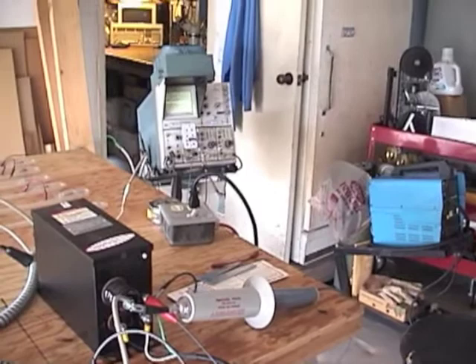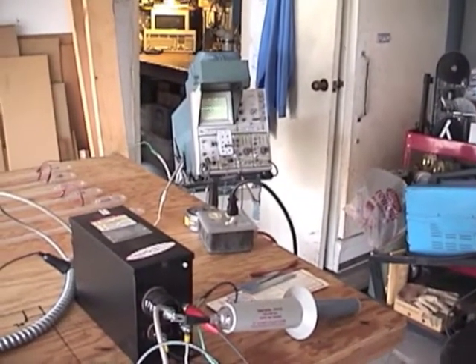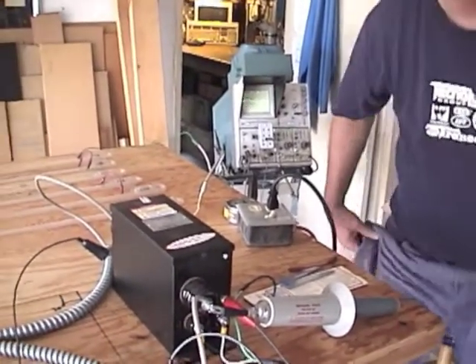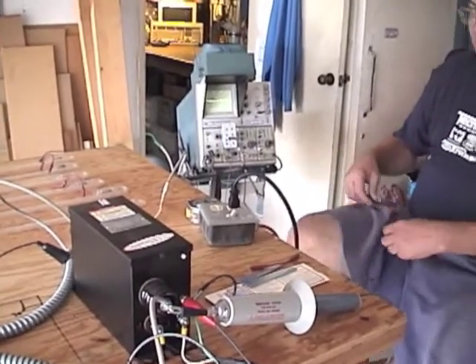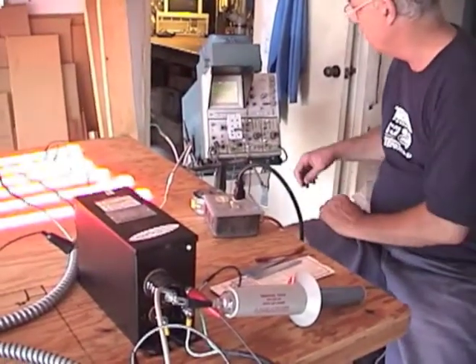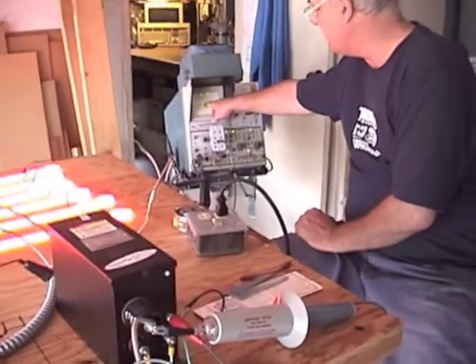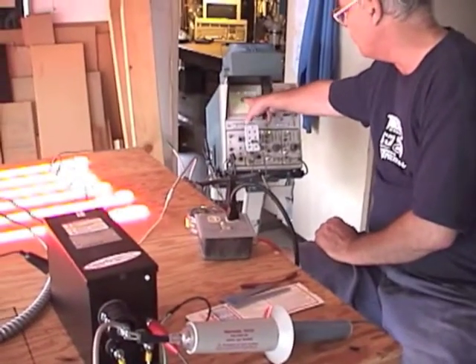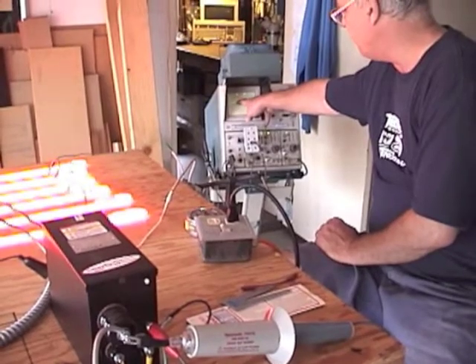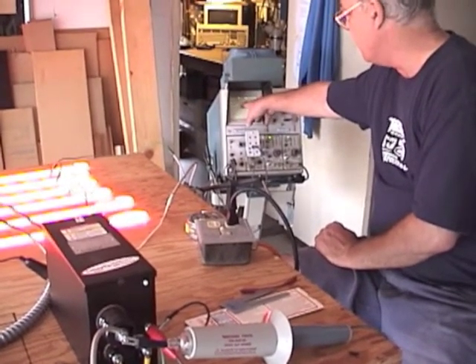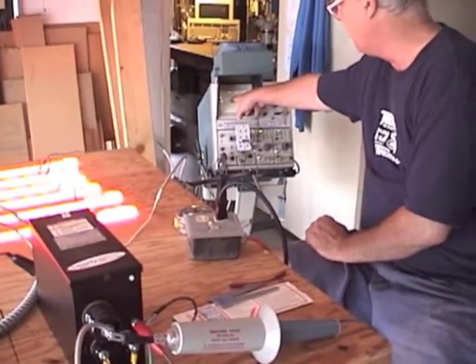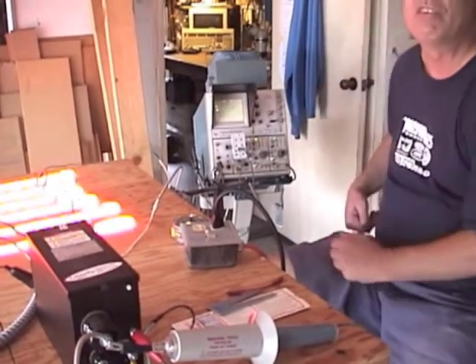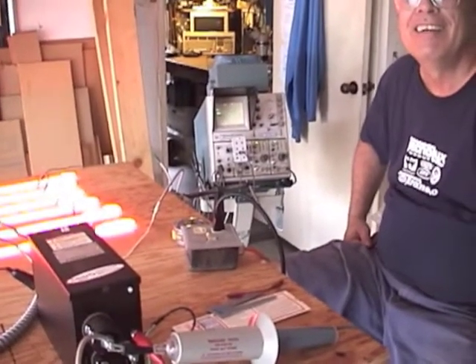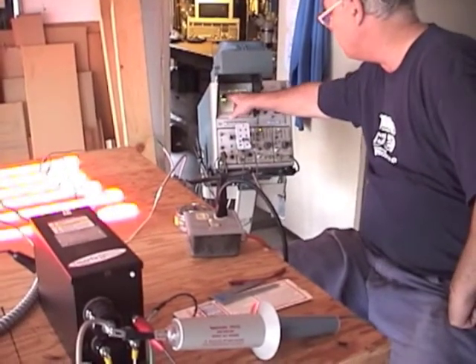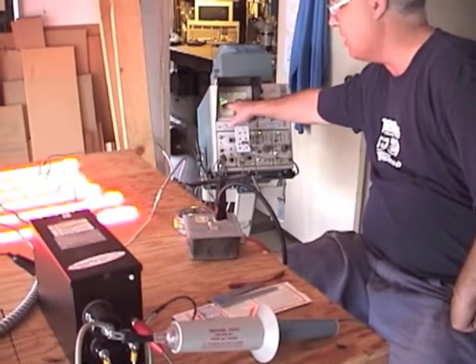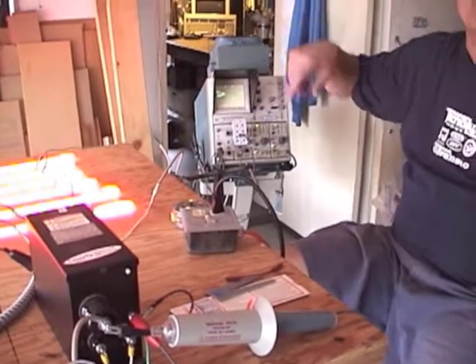So what this shows is, even measuring with a voltmeter, you won't see what's really going on, because high voltage probes and meters were originally designed for measuring DC. We found that they would run with AC, but they will not measure the high frequency. They'll measure the average. This is 5,000 volts per division, so 5 kV is that line right there. Basically it's measuring that average line. It's not measuring the peaks, which are double that. For every peak that goes up there, there's another peak at the other end that goes down towards zero, so the average is right in the middle.